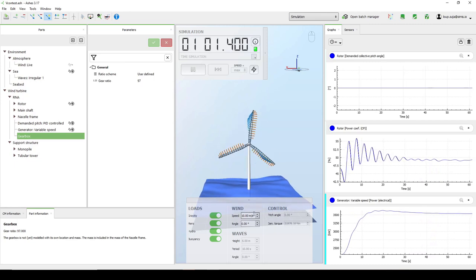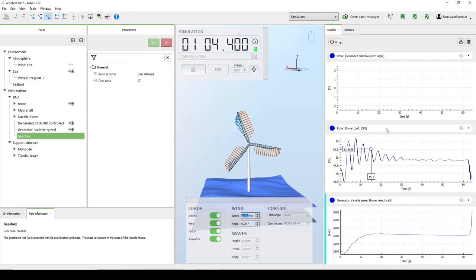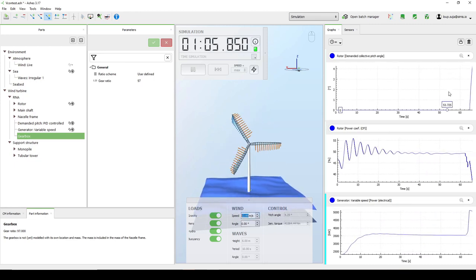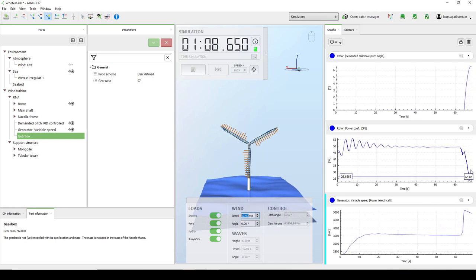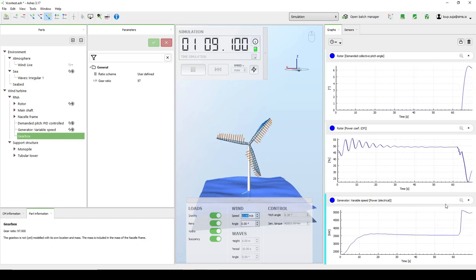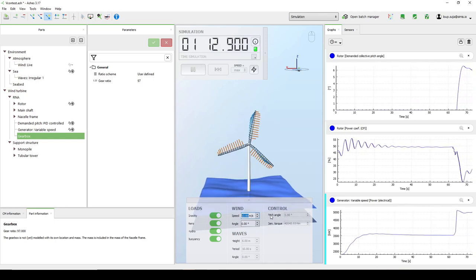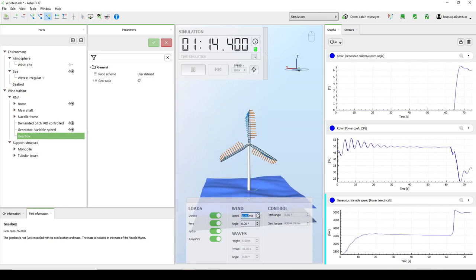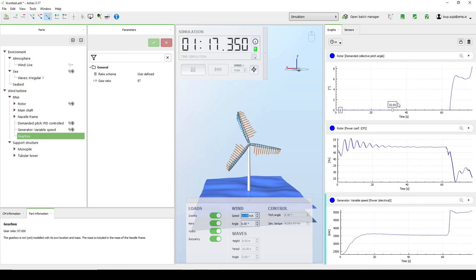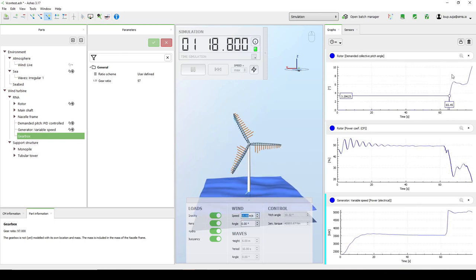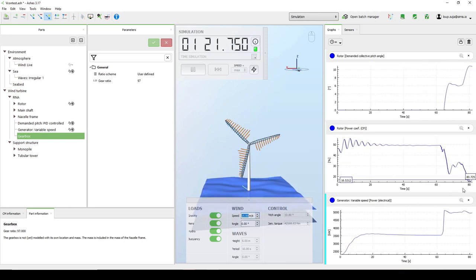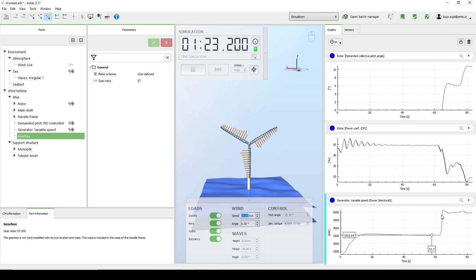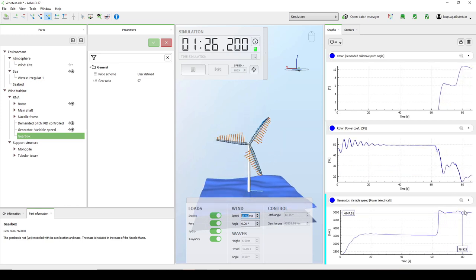If I increase the wind speed, the blades start pitching, decreasing the efficiency so that the power is now 5 megawatts. And if I increase the wind speed even further, the blades are pitched even more, decreasing the efficiency even further so that the power stays within what the generator can handle.